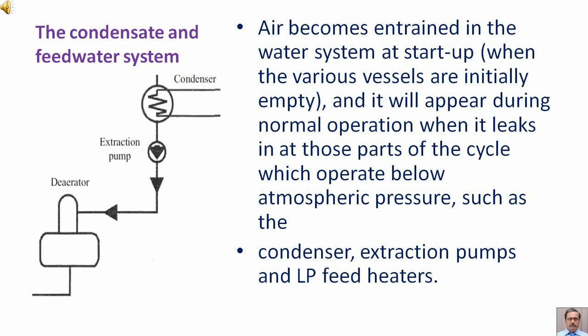Air becomes entrained in the water system at startup when the various vessels are initially empty. It will also appear during normal operation when it leaks in at those parts of the cycle which operate below atmospheric pressure, such as the condenser, extraction pumps, and LP feed heaters.